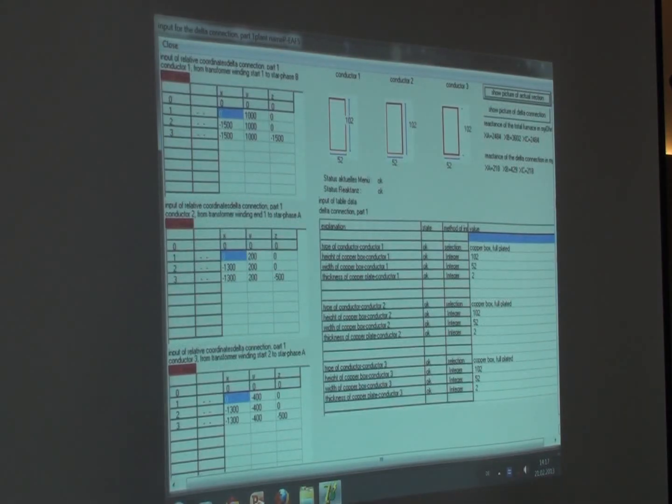I have written a few sentences in my instruction manual. You may remember: the following principles should be noticed for the design. Delta star conductors, on page 35. Delta star conductors have a relatively small reactance. The design of total reactances is going into high reactances. Therefore, delta star connections should be short. Delta star connections with 6 conductors are expensive and should be short.